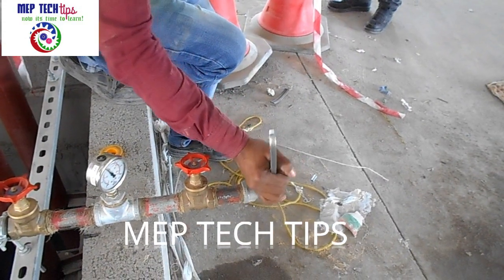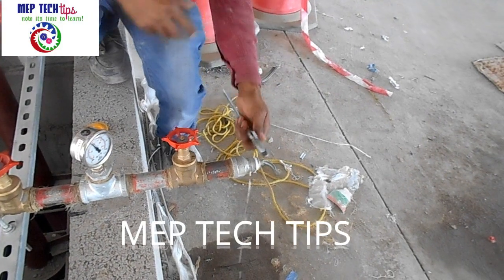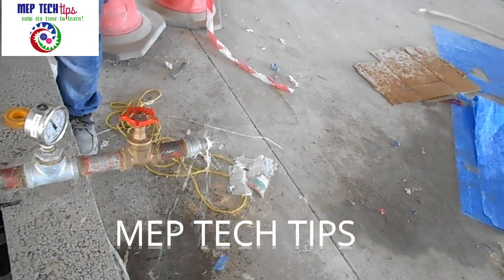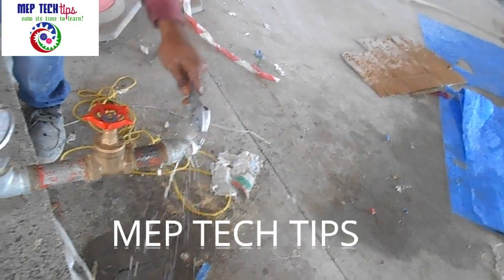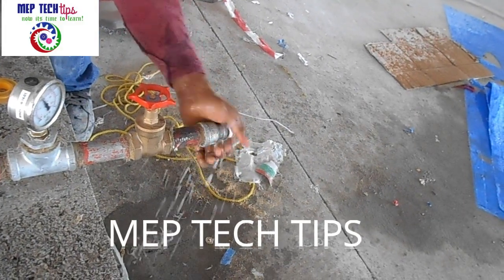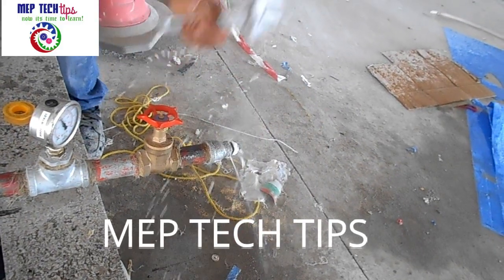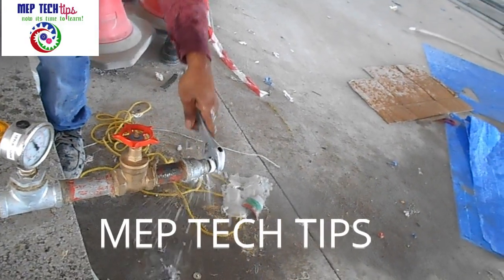We opened the gate valve and then opened the pressure gauge. Now we are opening the GI plug — but you must be very careful when opening the GI plug because the pressure is up to the end of the pipe. It will come out like a bullet, and it can hit a pipe wrench, which can fly to the other end and injure anyone standing nearby. You must clear the area before opening these kinds of fittings. You can see how the pressure comes out. By this way, we completed our pressure test and inspection with the consultant.